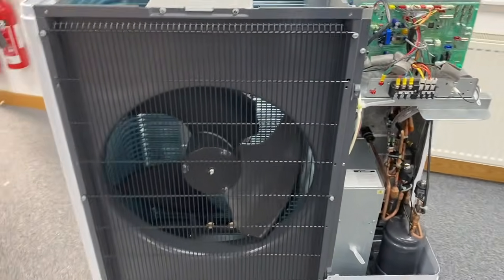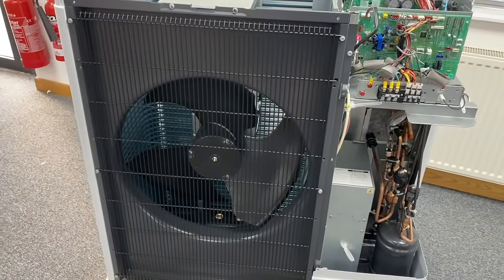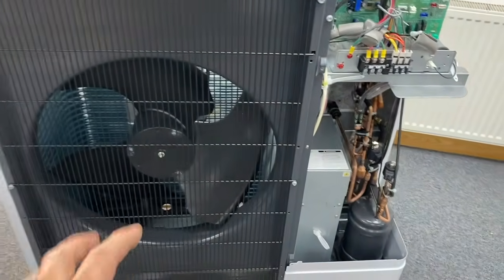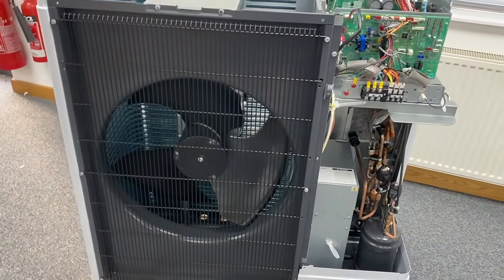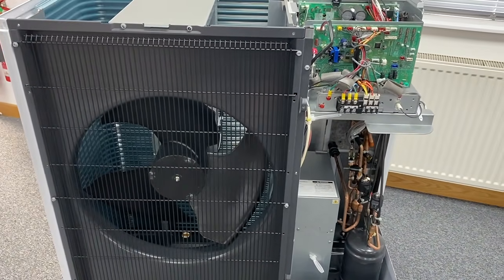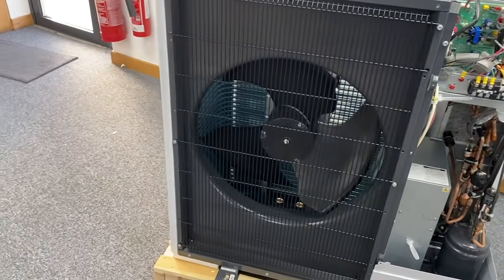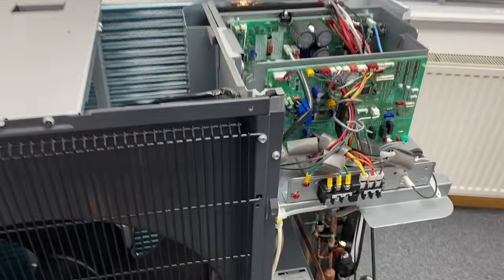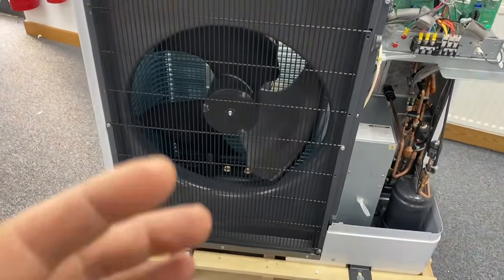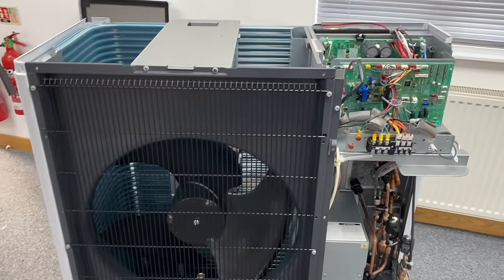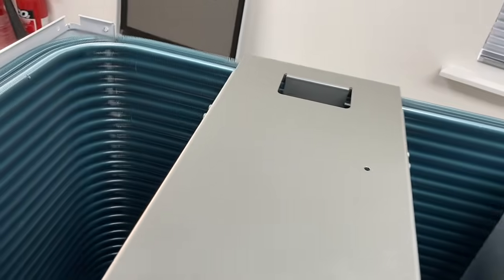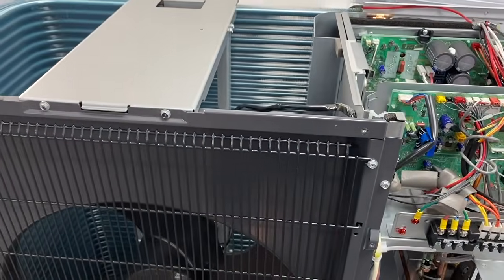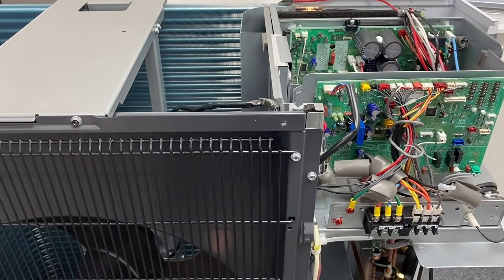So the fan's job then is pulling that energy out. If you ever stand in front of an air source heat pump, and when you install one, you probably will, you'll feel that the temperature is a lot colder in front of that fan than it is away from it. The ambient temperature coming through can be between 10 and 15 degrees lower as it pulls out through here. So if we're 15 degrees behind, we could be as low as 0 degrees in front. It's really using as much energy as it possibly can out of the air to generate the hot water we need for the home via the radiators and the hot water circuit.